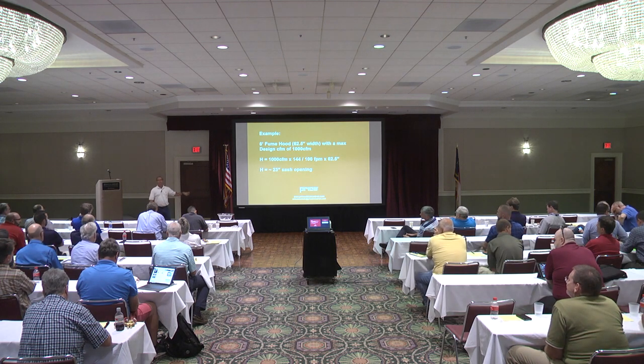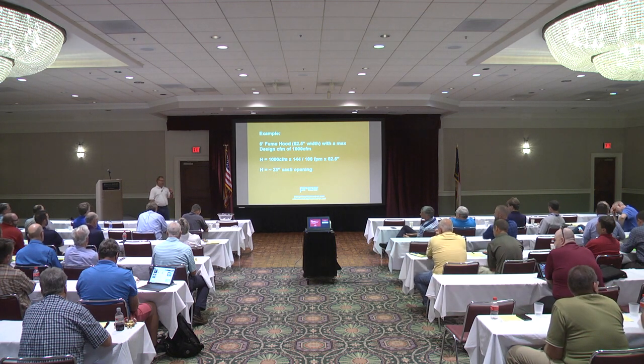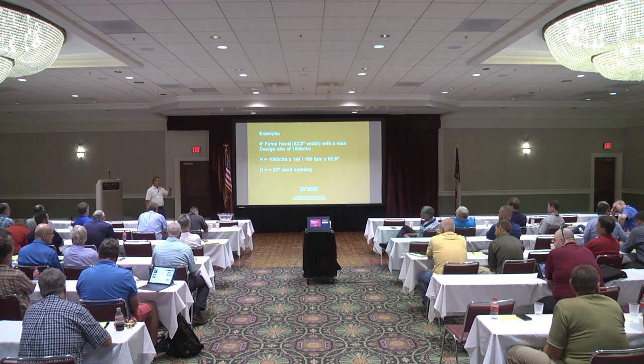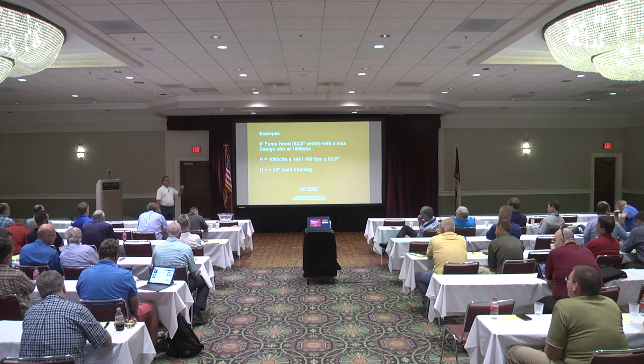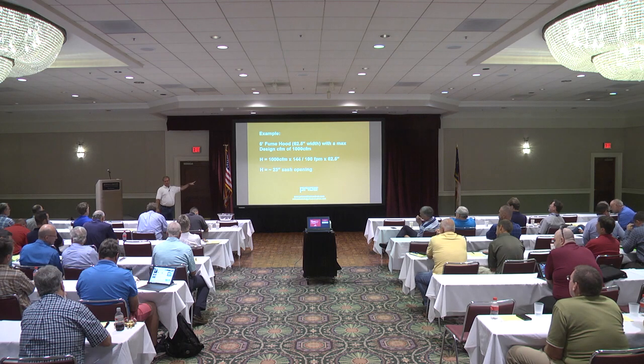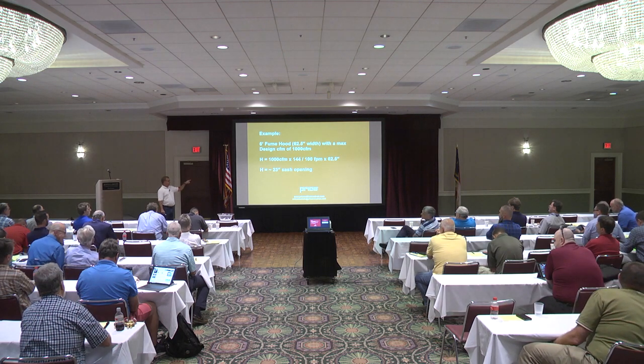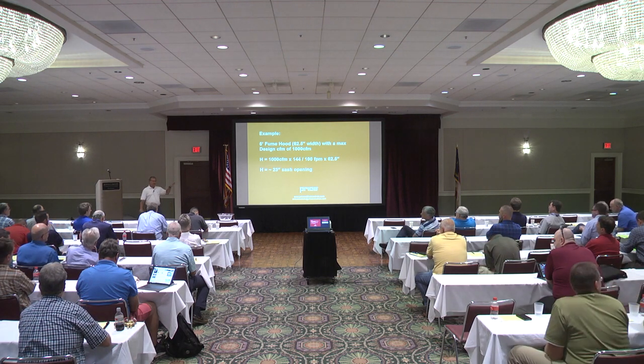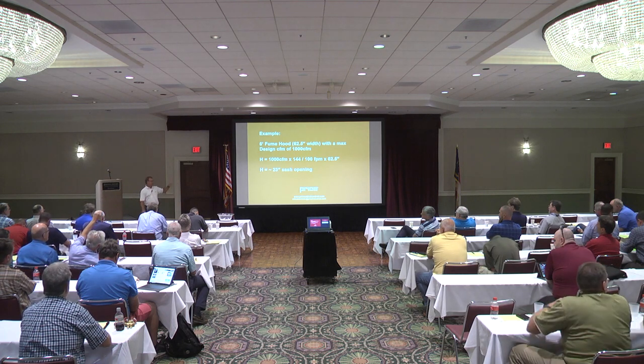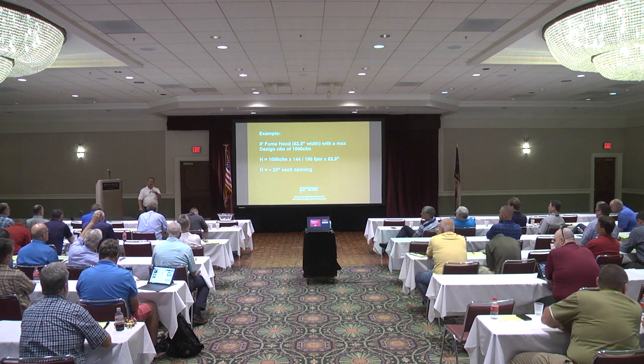And that's where the confusion comes in the lab test and balancing effort that we all go through, is that we get stuck on a sash height associated with a fume hood when it's really based on the CFM that's been designed, the width of the fume hood, and the velocity, not just a number, not just a height.